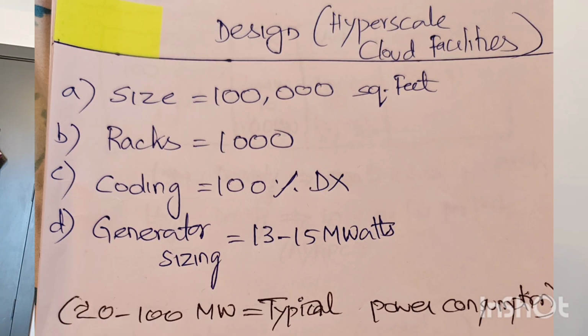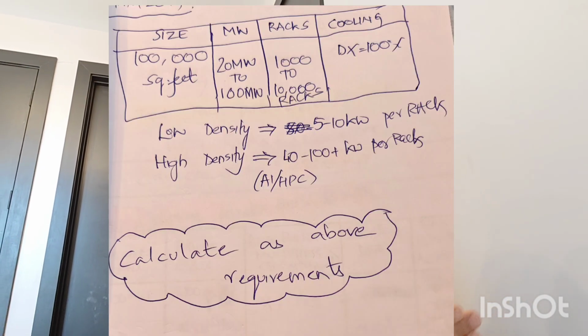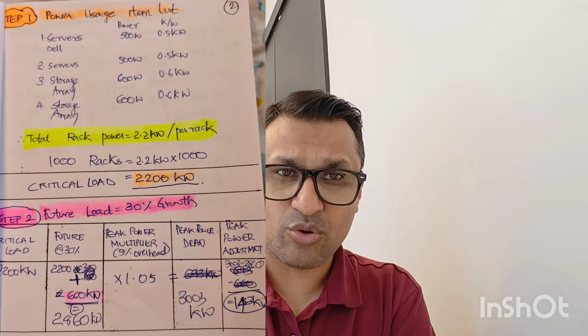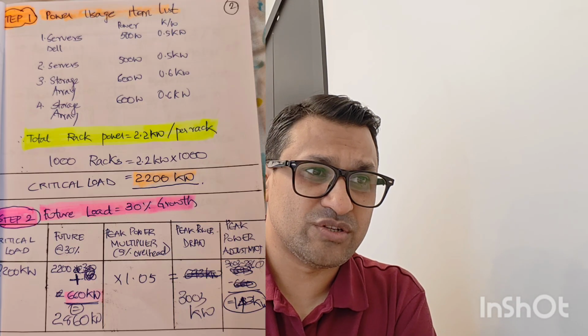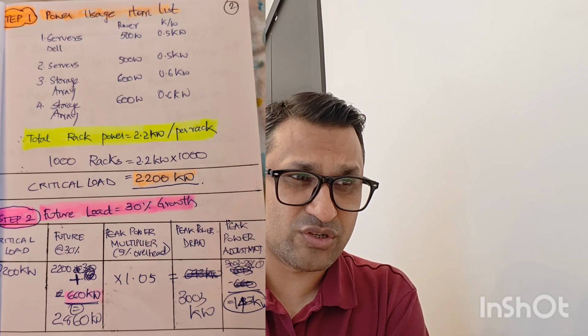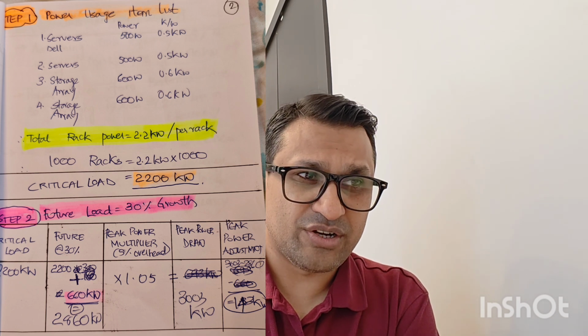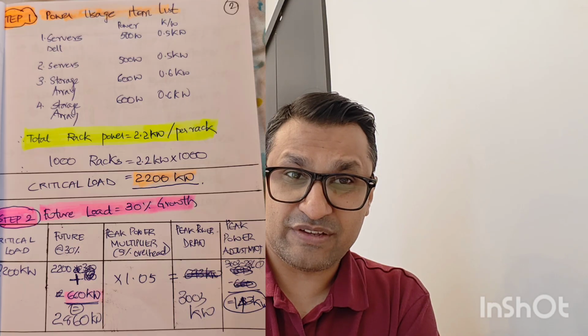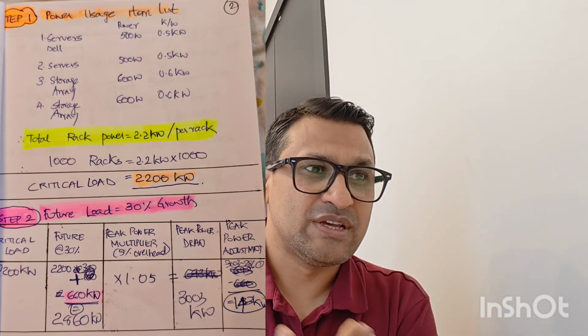So from today's learning point of view, we will be designing a 100,000 square feet data center area. And we are calculating for about 1,000 racks and completely DX cooling. Like in the smaller IDF closets, about 2,000 square foot of area, where we had used servers from Dell, if you're considering the same Dell servers with power of 500 watts, 0.5 kilowatt, here we will consider for design purposes two servers from Dell, both 0.5 kilowatt, and a storage array of 600 watts, and we'll consider two storage arrays just for design purposes. They could be hundreds. So 600 watts, 0.6 kilowatts. So that's the power usage item list.